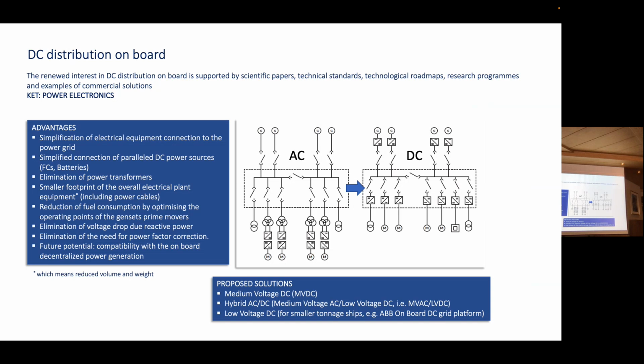The reduction of fuel consumption, because in a DC system we can operate the prime mover of the generation system at variable speed, so we can set this prime mover at its optimal point of operation and reduce the consumption of fuel. This is not possible in an AC system because we are constrained by the fixed frequency that in ships is usually 50 Hz or 60 Hz, and so the prime mover has to run at fixed speed. There are other advantages from the point of view of power quality, and as a future potential, this system is well compatible with the onboard decentralized power generation, so the two paradigms are compatible between them.